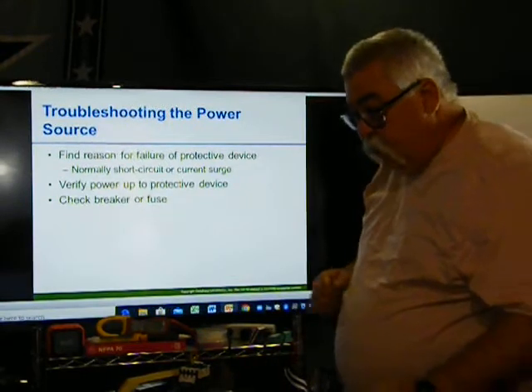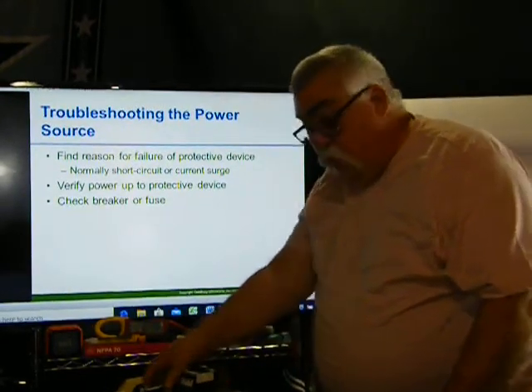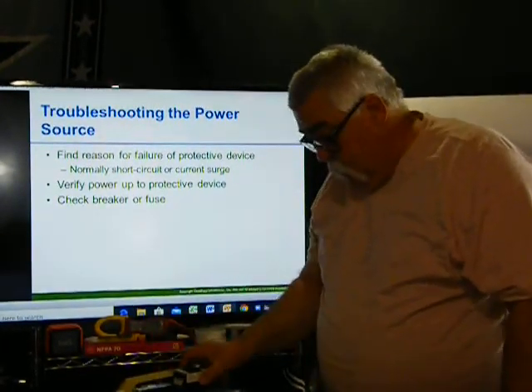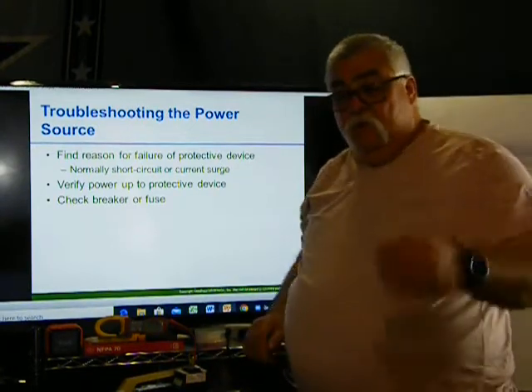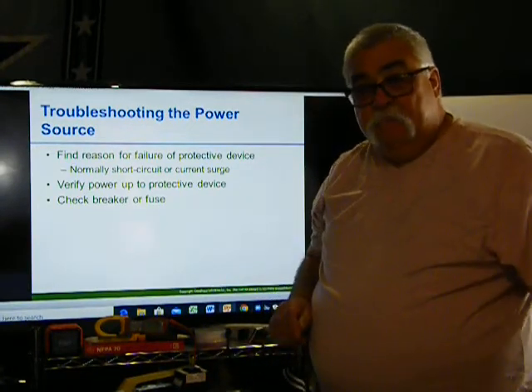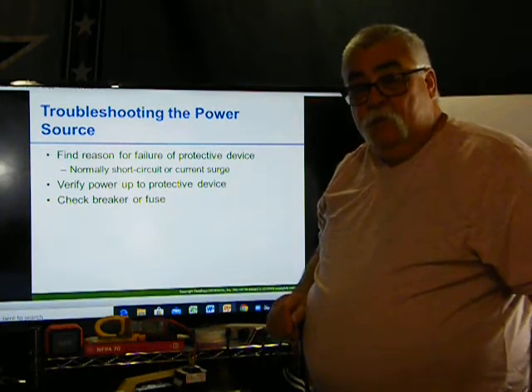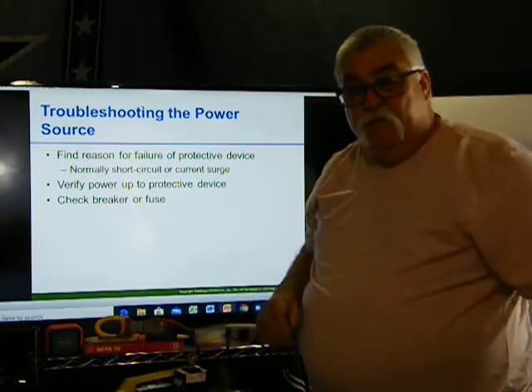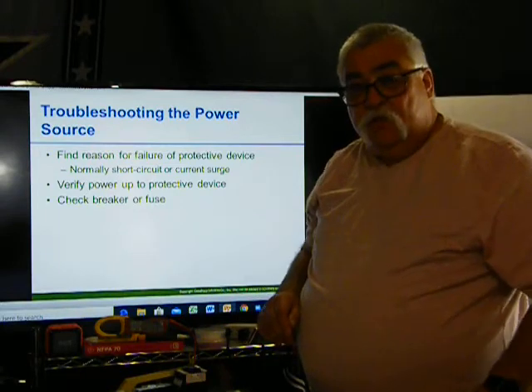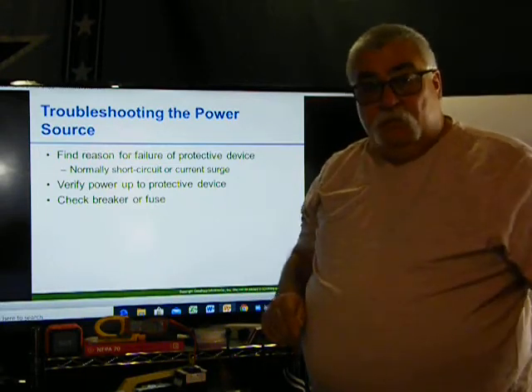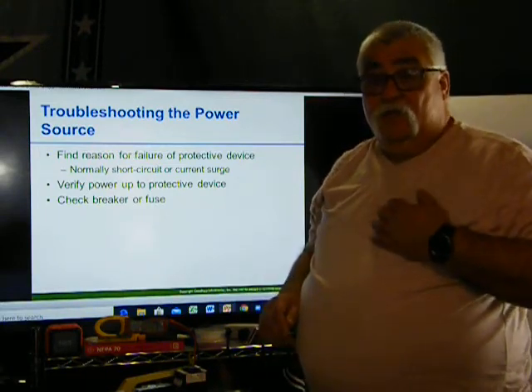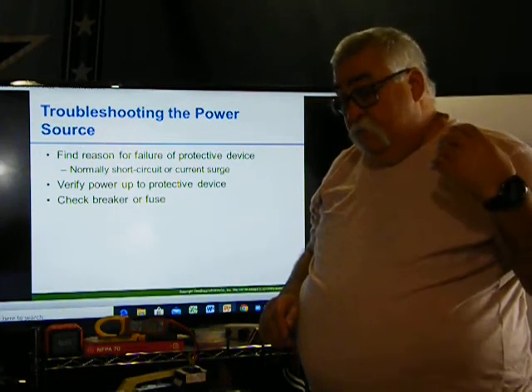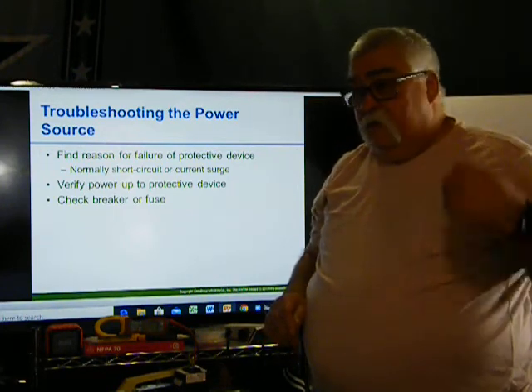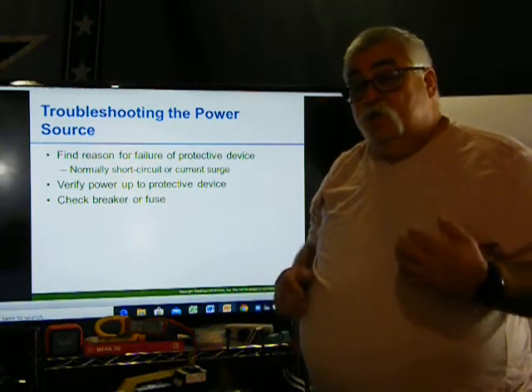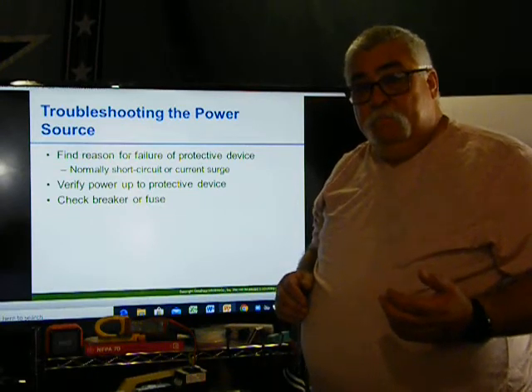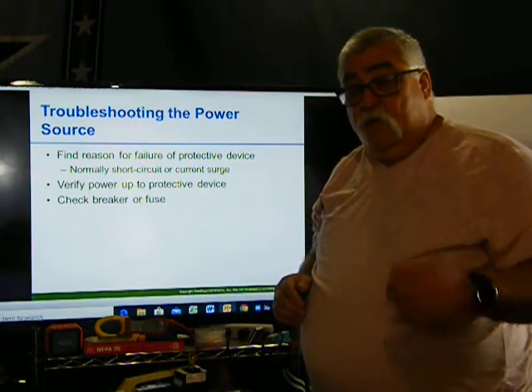I have the contactor that I showed you all at school that happened to me at work. I got called in and they said, oh yeah, the overload's tripped, can you change out the overloads? I said, sure, and went to do it. He goes, oh no, we're doing preventive maintenance and I think we just tripped the overloads. So I took it as they already had checked everything. They did preventive maintenance, motor check, clean out, whatever they did. So I assumed that it was just the overloads, and I went and changed the overloads.